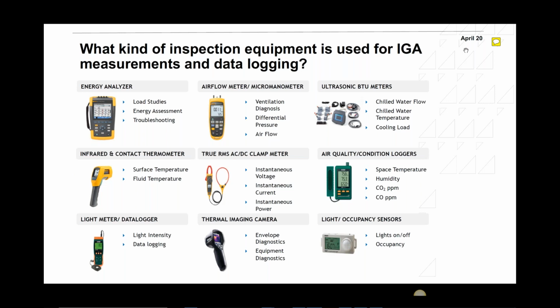Light meter, thermal imaging camera: I can use that for envelope diagnostics if I want to check if there's proper insulation or not. If I take a photo of a wall, it might show me where there is insulation and where there's not, where there's some heat seeping in or out of the building. I can use it also for equipment diagnostics, so I can look at electrical panels to see if there are any points that have been heating up. I can use occupancy sensors for lights, so I can put that sensor and see if there's any movement or whether the lights are on or off.